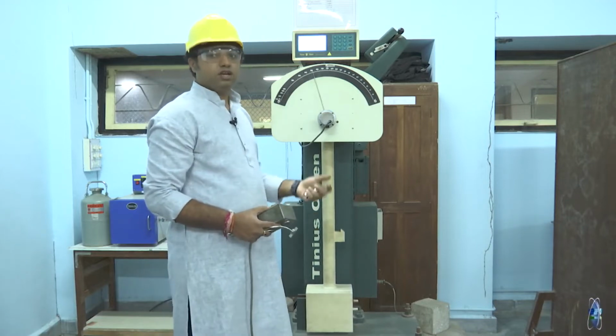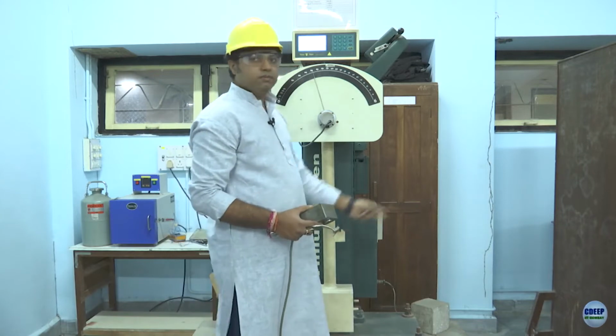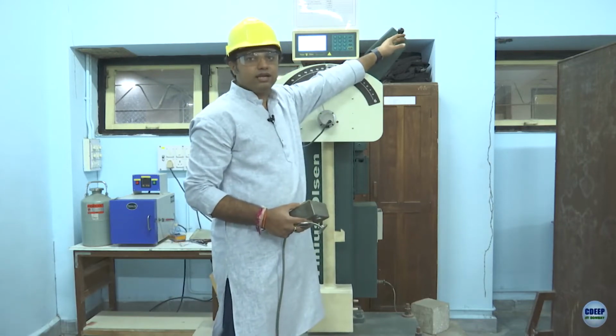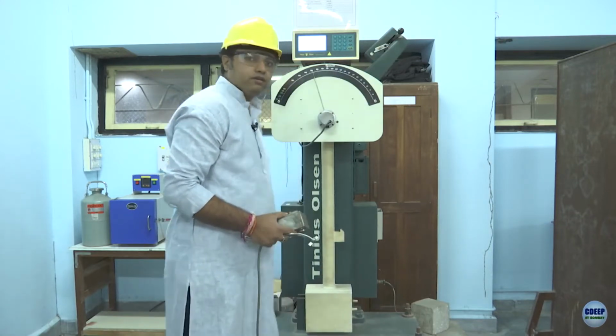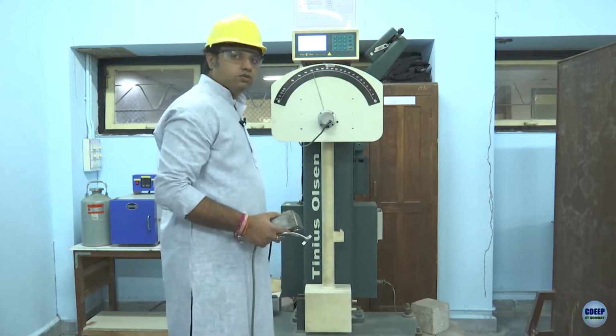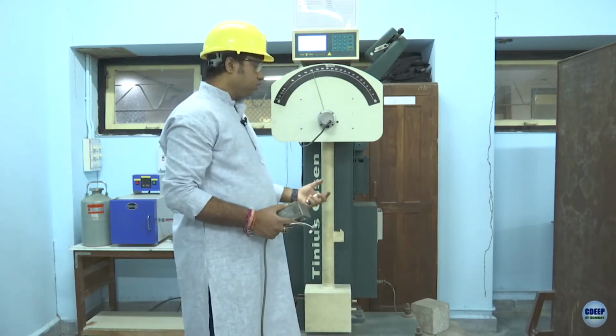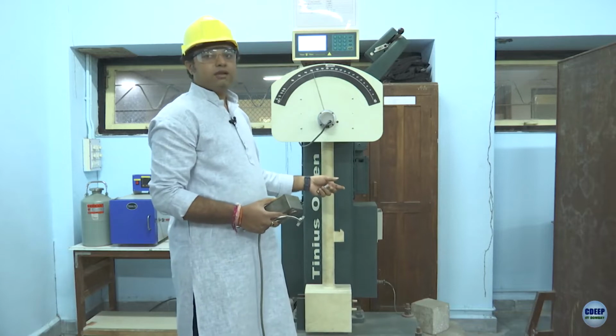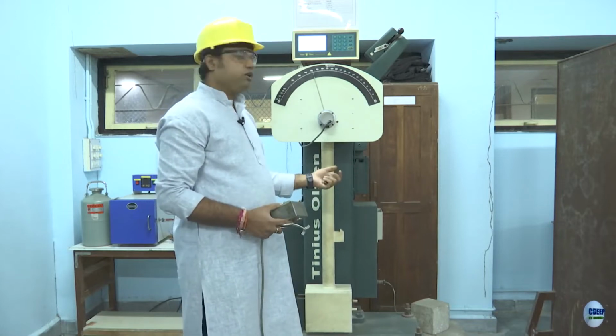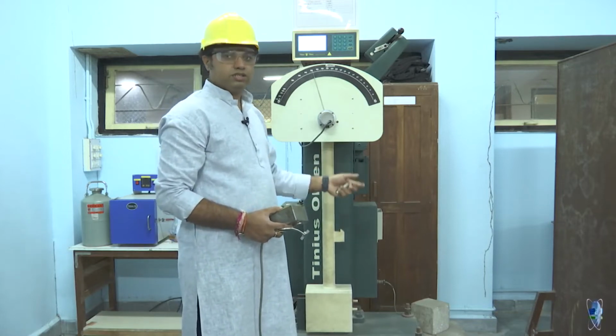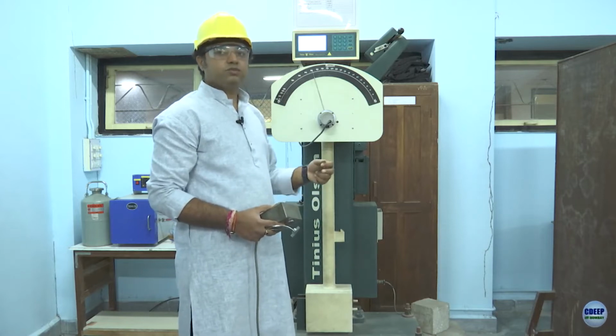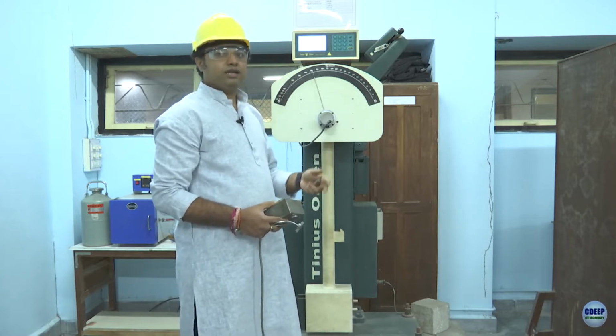The second point is friction loss. As this pendulum is latched at a particular height, which we call H1, it moves from that height to H2. Air resistance and other parameters come into picture, so we need to account for that. That's why we do the friction loss test; basically, the friction loss has to be subtracted from the final value.